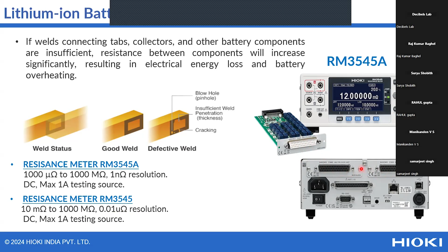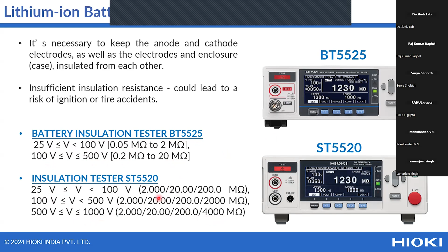Second is the insulation test. It is required to test the insulation between the anode and the cathode. If the resistance between these is low, then there is a chance of a fire accident. So you can use these two insulation testers, BT5525 and ST5520, with different voltage and resistance ranges. BT5525 is available from 25 volt to 500 volt, and the resistance ranges from 0.05 mega ohm to 20 mega ohm. And for ST5520 you can apply up to 100 volt and check the insulation resistance of a battery.